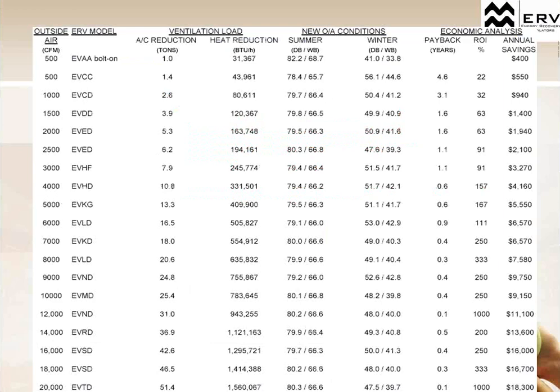We've broken down multiple different CFMs and cabinets and what we've seen as an average tonnage reduction and heat reduction on the system. So in all the different applications and jobs that we've done, we've summarized conditions for central Illinois, anywhere from 500 CFM to 20,000 CFMs. You can see a 5,000 CFM system on average, 5,000 CFM of outside air. Let me clarify, that's 5,000 CFM of outside air coming in through the ERV.